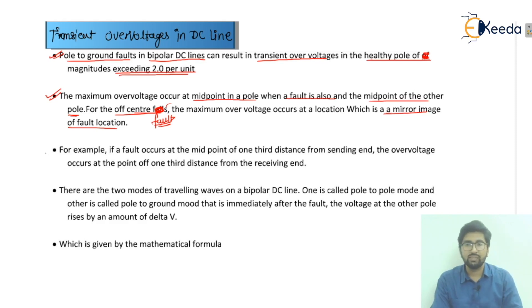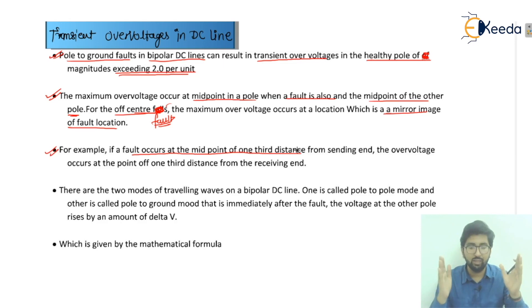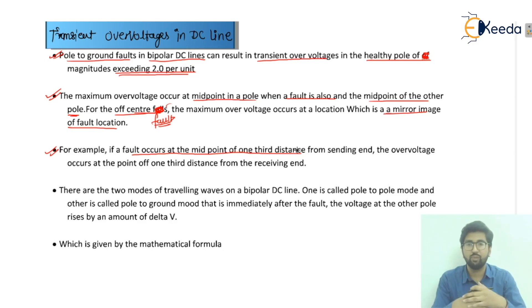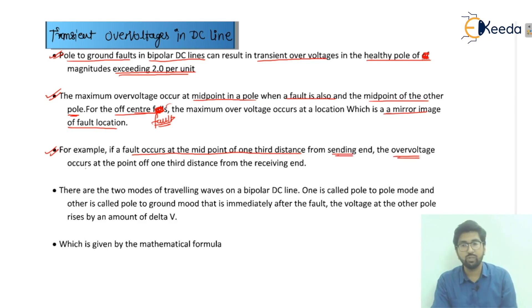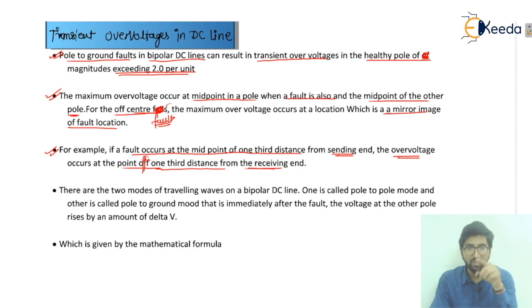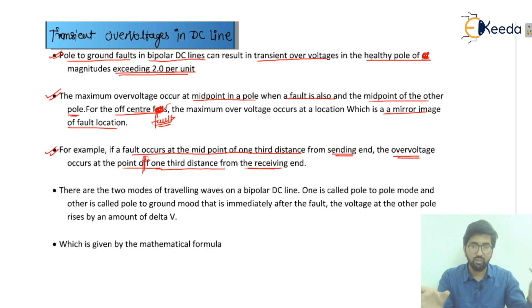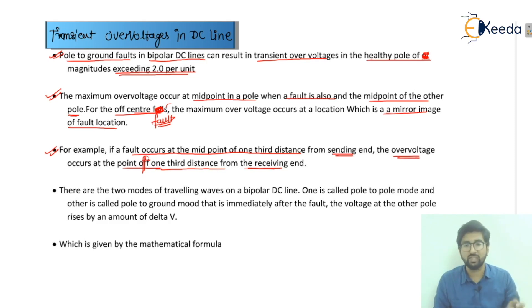Let us take an example: suppose we have a 100-kilometer line. If the fault occurs at one-third distance from the sending end, that is 33.33 kilometers from the sending end, then the overvoltage will occur at one-third distance from the receiving end, that is 33.33 kilometers from the receiving end. So it is actually the mirror image — whatever the distance is from the sending end, that same distance applies from the receiving end.